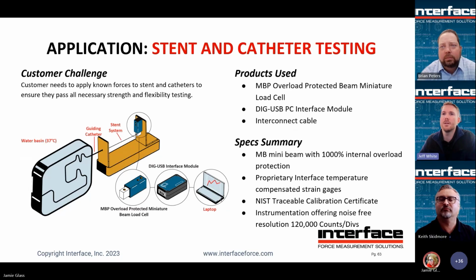All right. Well, an MB load cell was used in this stent and catheter testing for medical application. So the customer needed to apply known forces to the stent and catheters to ensure they pass all necessary strength and flexibility testing. The MB overload protected load cell was selected. We used the DIG USB, a good fit for a noise-free environment. MB proprietary interface strain gauges, NIST traceable calibration, important for the medical industry, and resolution up to 120,000 counts with the DIG USB interface module.